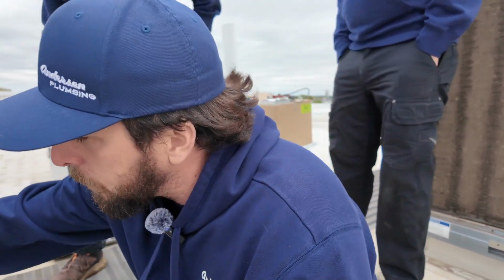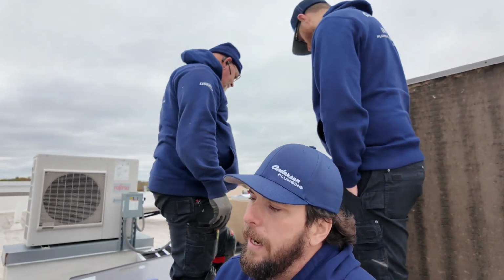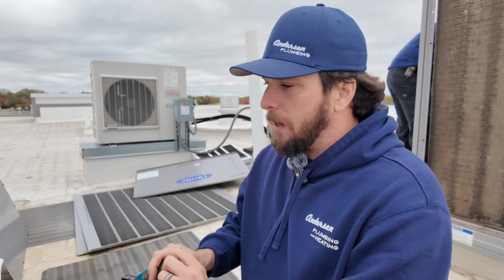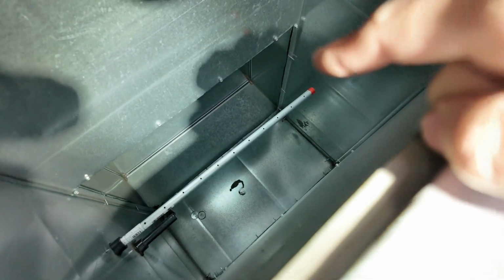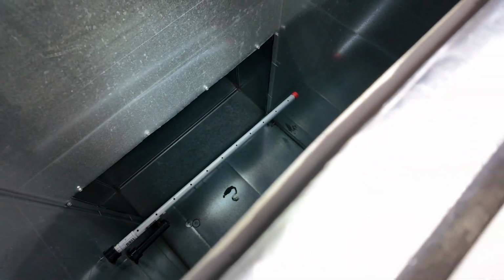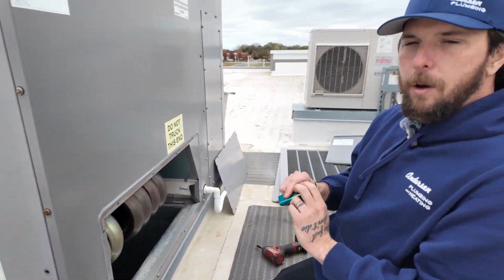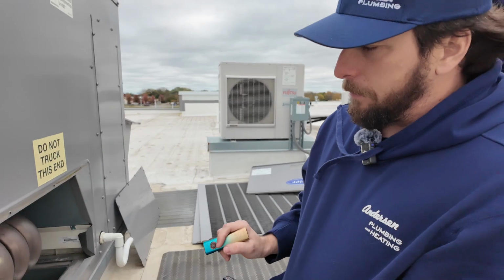Now, if you have any sort of a crack or a perforation or a tear or a rust hole or anything like that in the heat exchanger, the carbon monoxide from the gas being burnt is then being released into the conditioned space. So basically, if you look straight down here, this is your ductwork. So this is what goes out to the whole building in order to supply the heat. So if we have carbon monoxide leaking from one of these units, it's going down into the conditioned space where everybody's hanging out. And obviously we all know that breathing carbon monoxide is less than ideal.